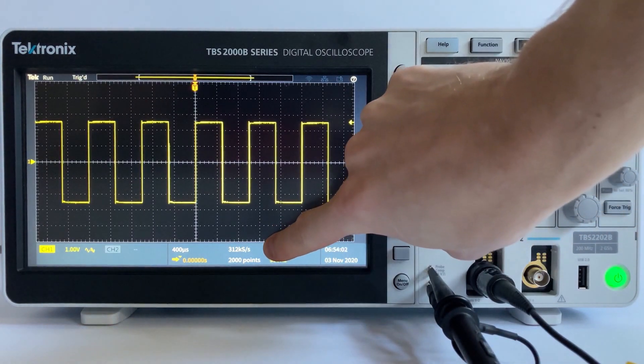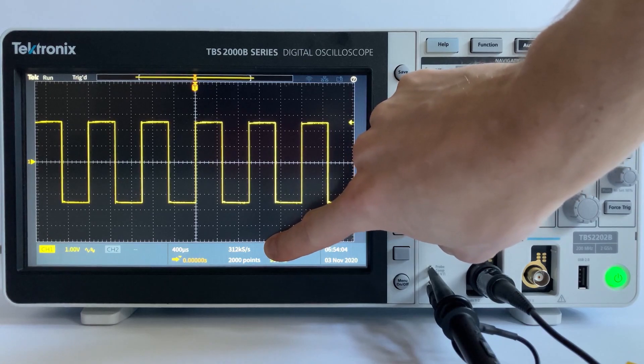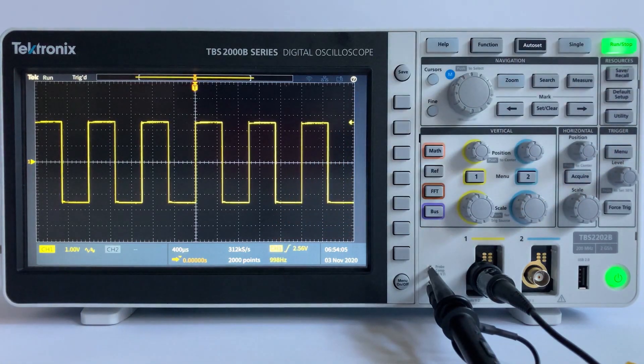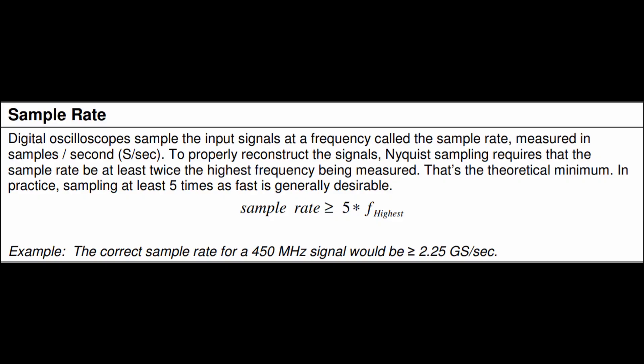Digital oscilloscopes sample the input signal at a frequency called the sample rate, measured in samples per second. To properly reconstruct the signals, the Nyquist sampling theorem requires that a sample rate be at least twice the highest frequency being measured. That's the theoretical minimum though. In practice, sampling at least five times as fast is generally desired.